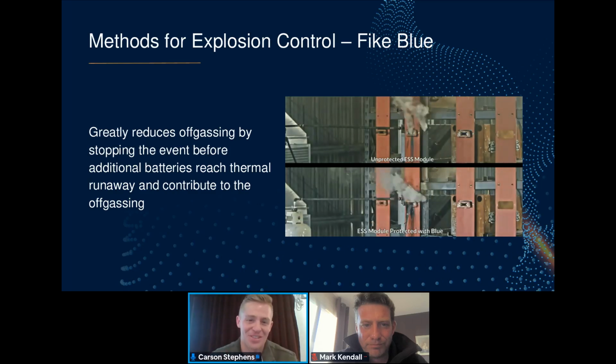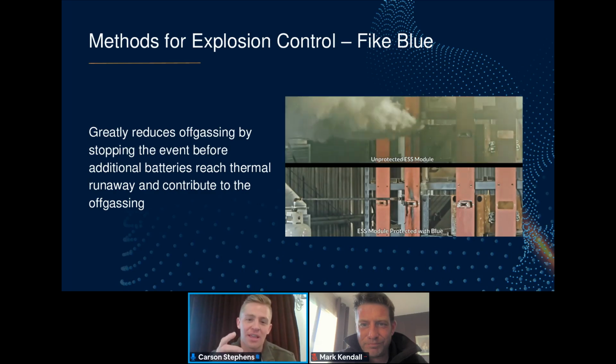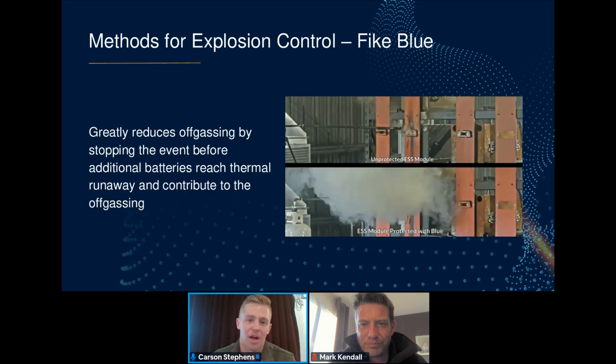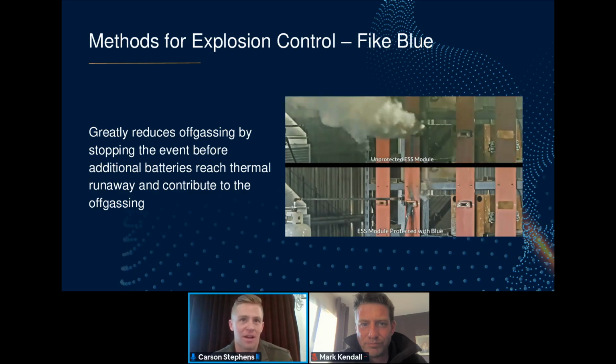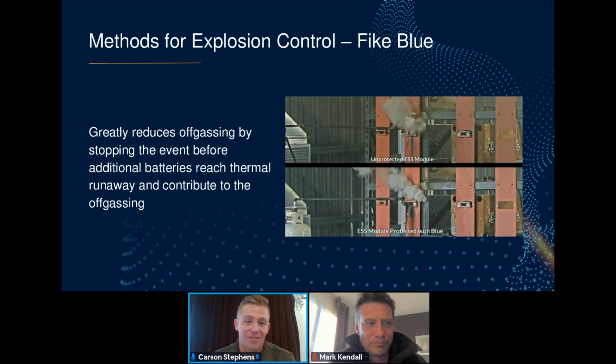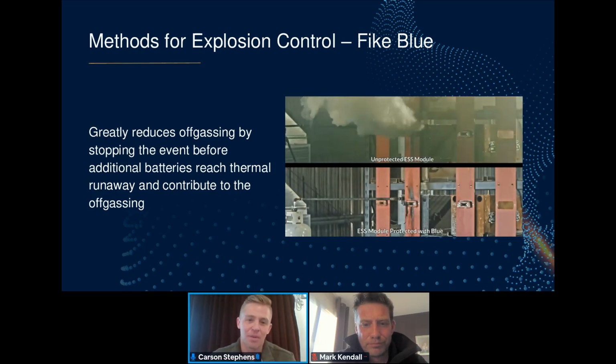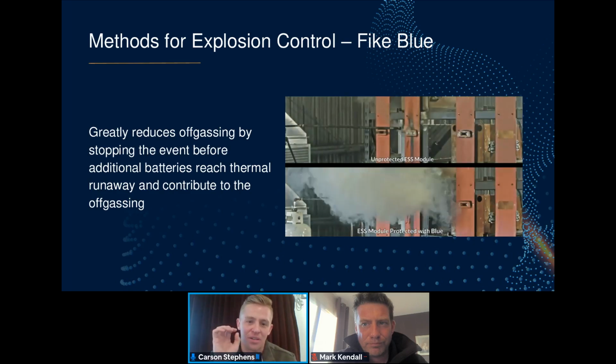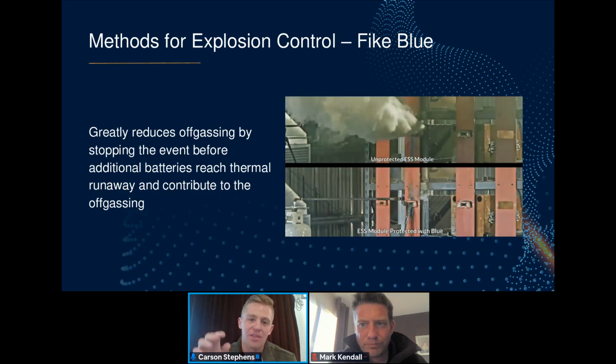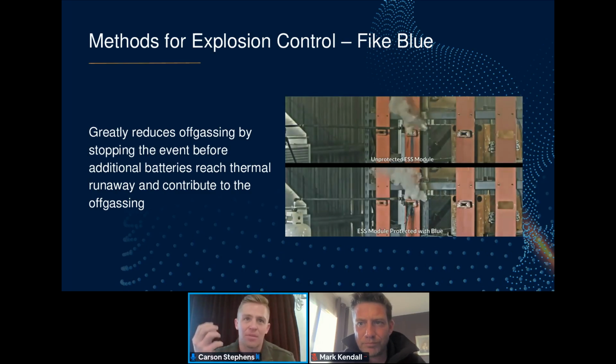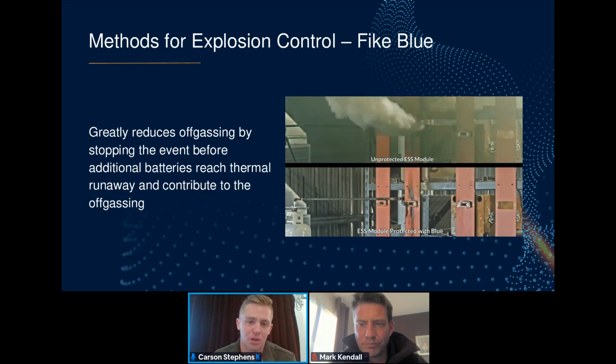The thermal runaway you can see is going from cell to cell, and how you know it's going from cell to cell, other than the thousands of thermocouples and temperature gauges that we have on this enclosure at our remote testing facility, is that you can visually see it. Nobody's in here. This is a camera. But in the top part, you can see that it's leaking smoke, and then it kind of suppresses just a little bit, but then it'll resurge with another huge plume of smoke.